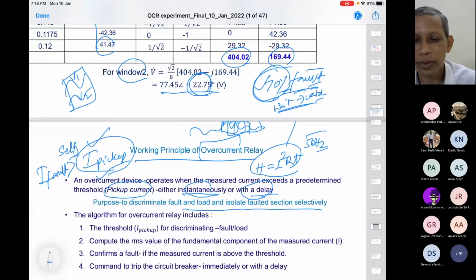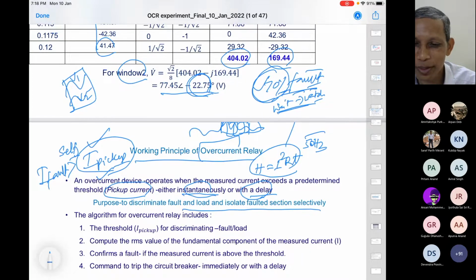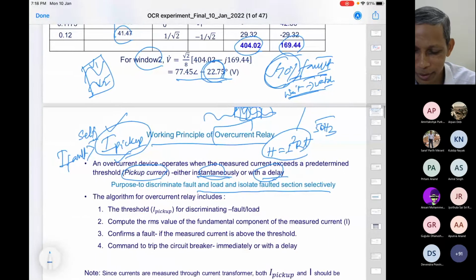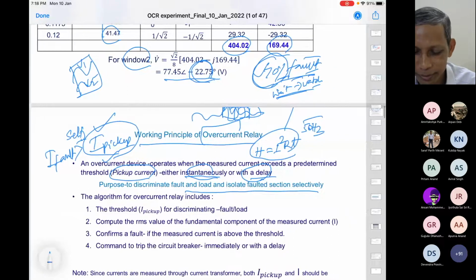That is nothing but what we call auto reclosing. Trip, then auto reclose after some time, because most of the faults will vanish by that time. Okay? So auto reclosing is very common in transmission systems. Transitory faults versus permanent faults is more of a high voltage system matter. But in low voltage systems with cable, most of these are permanent faults. Is that okay?